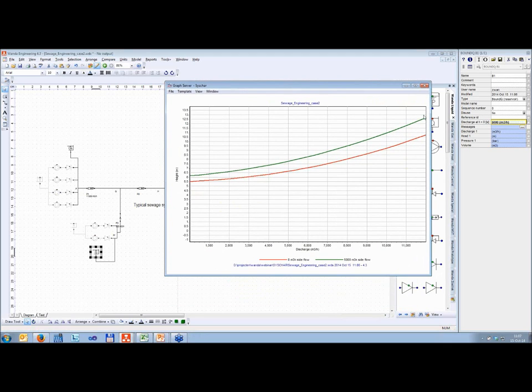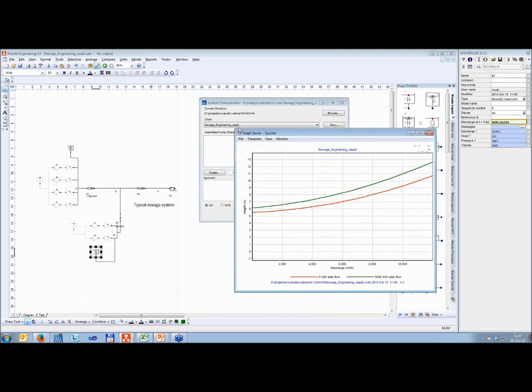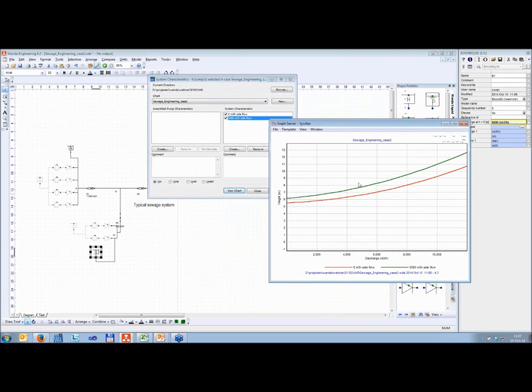Now you can see it makes a difference because if this pumping station is supplying, the pressure will rise at the connection point. So the other pumping station will see a higher head and needs to supply more head to reach the same discharge point. Of course, for a much more complex system you can do the same thing.